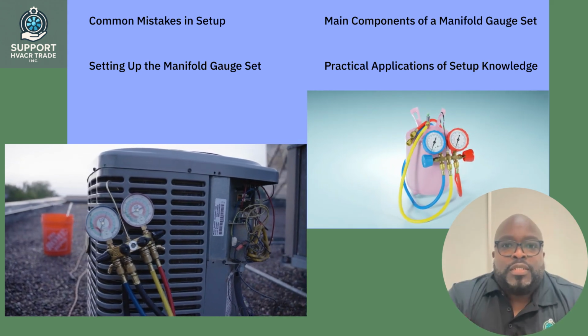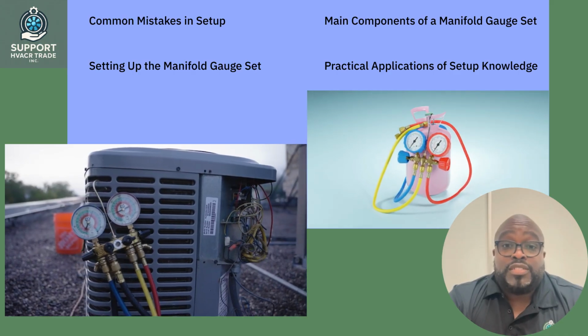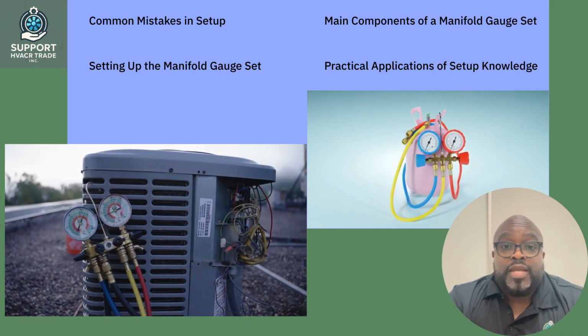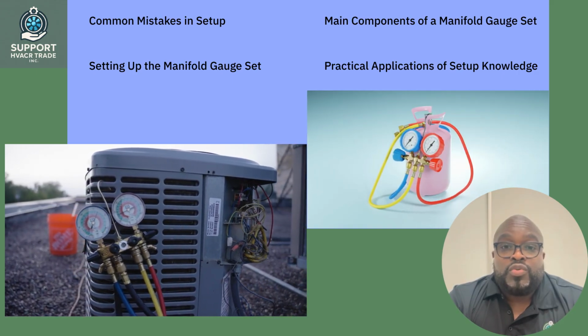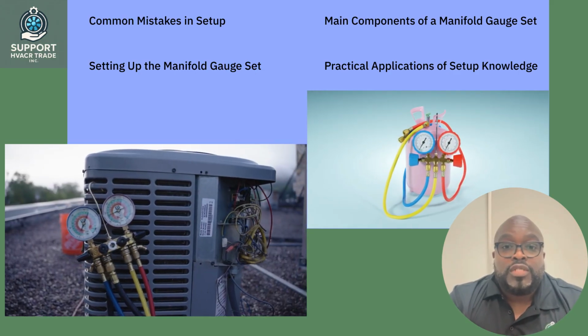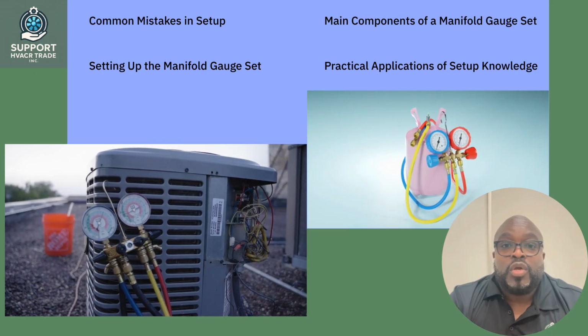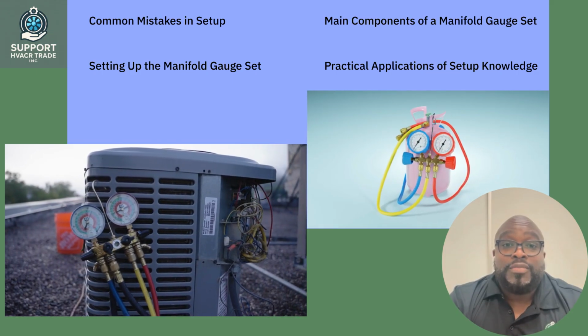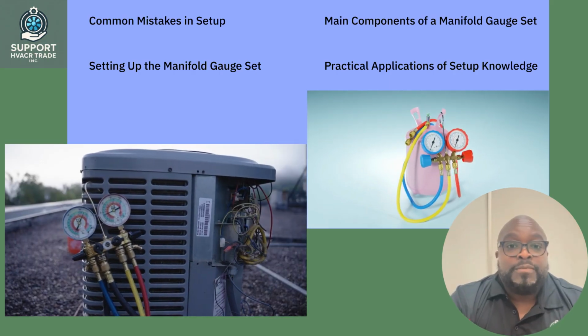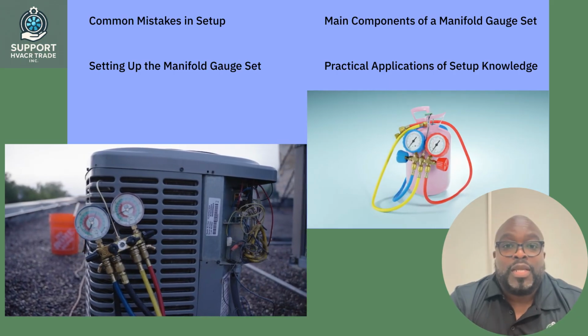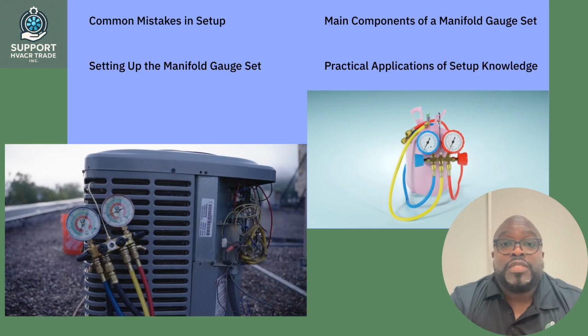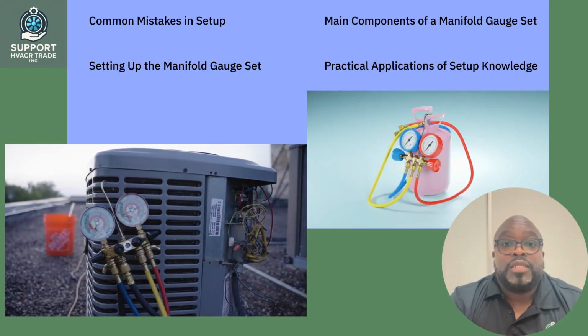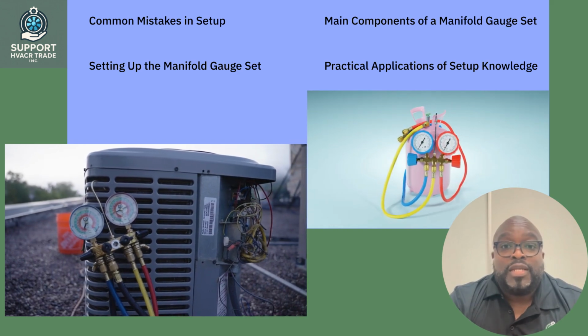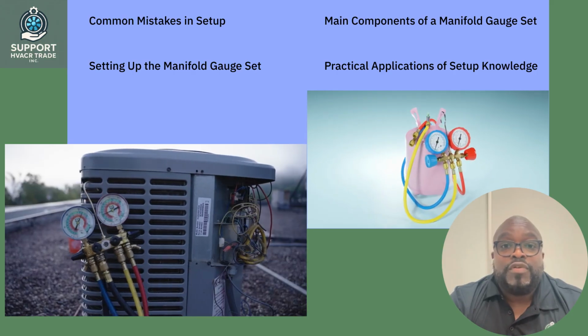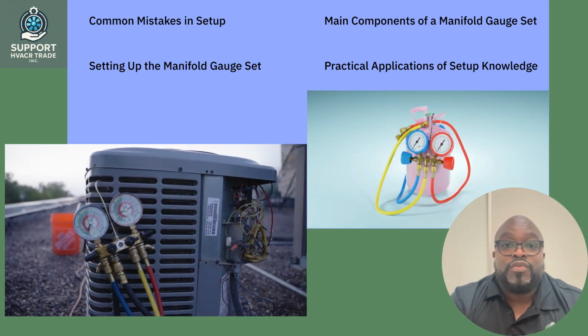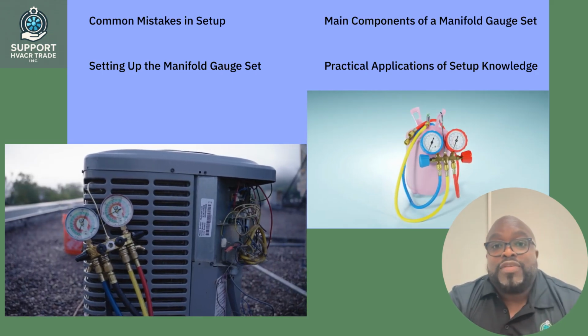Setting up the manifold gauge set. Proper setup is essential for accurate measurements and safe operation. Follow these steps to set up your manifold gauge set. Inspect the equipment. Before use, check all components for wear or damage, ensuring that hoses and gauges are in working order. Connect the hoses. Attach the red hose to the high-pressure side and the blue hose to the low-pressure side of the manifold. Make sure the connections are secure to prevent leaks. Attach access fittings. Connect the other ends of the hoses to the system's access fittings, ensuring they are properly seated. Open the valves. Once everything is connected, open the valves on the manifold to allow refrigerant flow. By following these steps, you will set up your manifold gauge set for effective use in diagnosing HVAC systems.